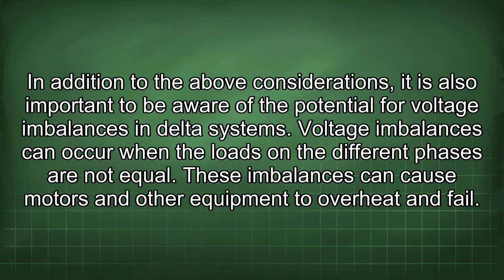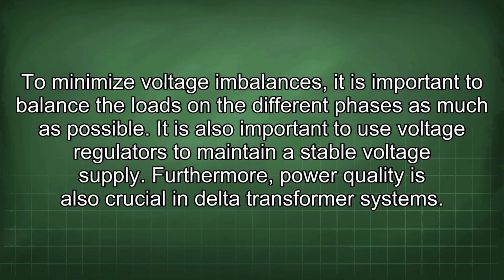In addition to the above considerations, it is also important to be aware of the potential for voltage imbalances in delta systems. Voltage imbalances can occur when the loads on the different phases are not equal. These imbalances can cause motors and other equipment to overheat and fail. To minimize voltage imbalances, it is important to balance the loads on the different phases as much as possible. It is also important to use voltage regulators to maintain a stable voltage supply.